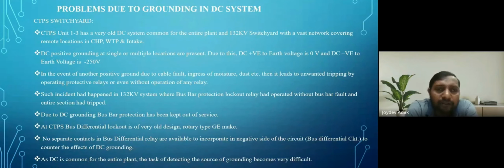So the first fault is existing in the DC system, and during a second fault in the bus differential protection system, the circuit contact of the bus differential relays gets shorted, and the bus differential protection operates several times without any relay indication. It creates failure of the total system, and total power failure occurred two to three times. So our aim was how to identify this. First, we have to make this DC voltage ideal.